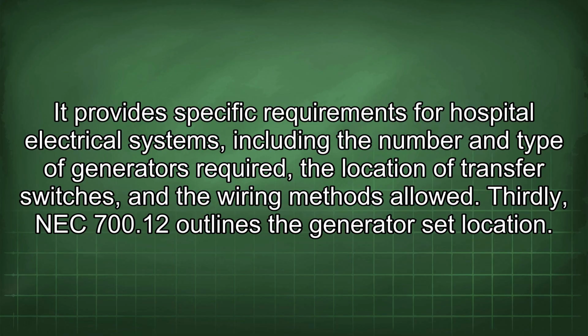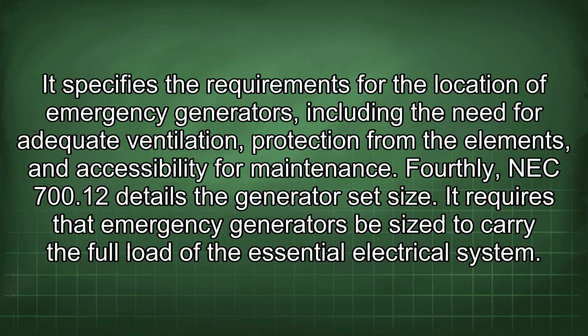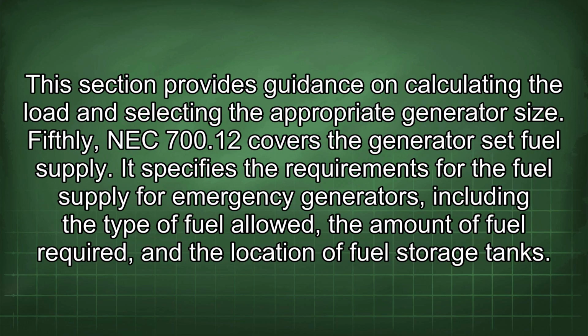Thirdly, NEC 700.12 outlines the generator set location. It specifies the requirements for the location of emergency generators, including the need for adequate ventilation, protection from the elements, and accessibility for maintenance. Fourthly, NEC 700.12 details the generator set size. It requires that emergency generators be sized to carry the full load of the essential electrical system. This section provides guidance on calculating the load and selecting the appropriate generator size.